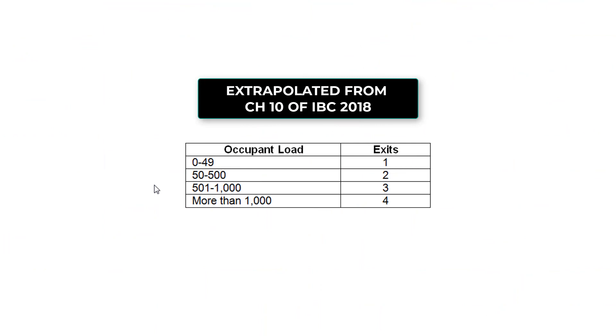The following table stipulates the number of exits for various occupancies: 0 to 49 occupants requires 1 exit; 50 to 500 requires 2 exits; 501 to 1,000 requires 3 exits; and more than 1,000 requires 4 exits.